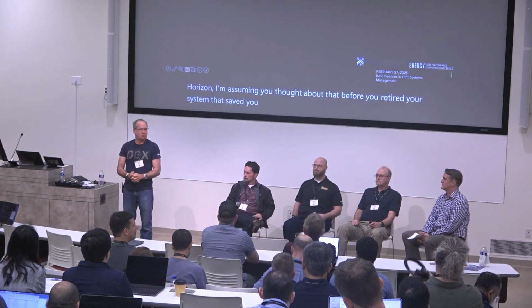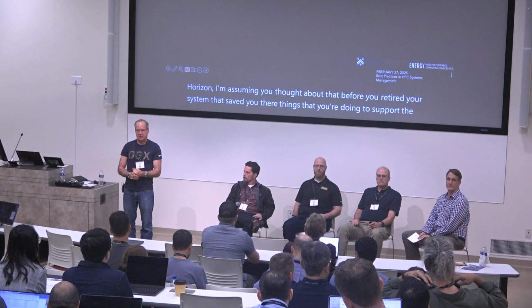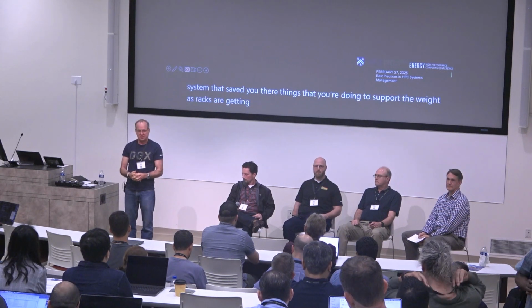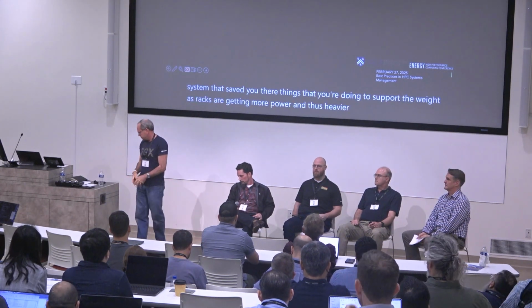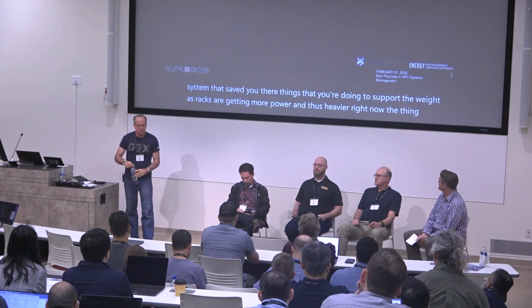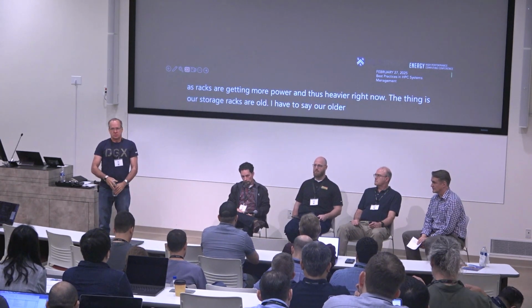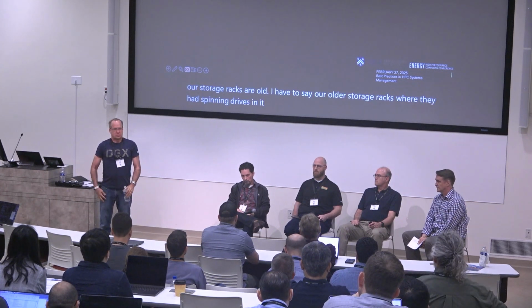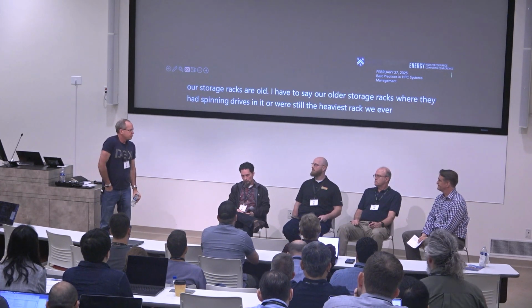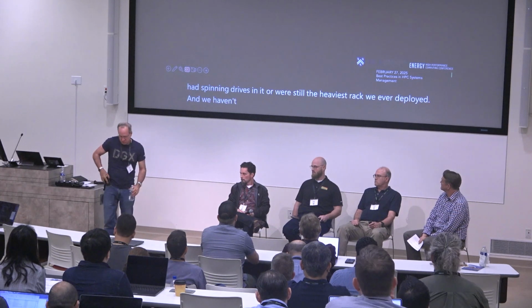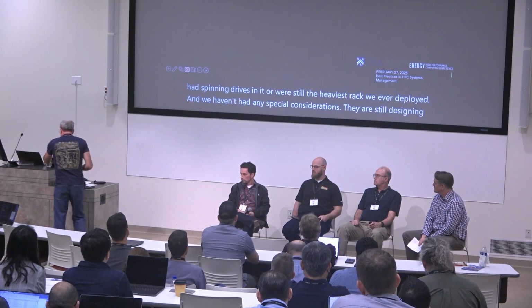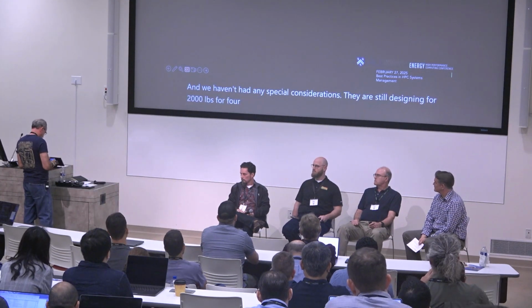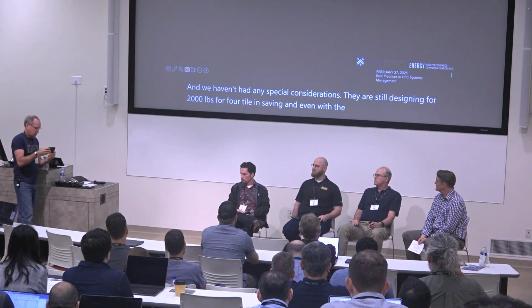Things that you're doing to support the weight as racks are getting more power and thus heavier. Right, now the thing is, our storage racks, the older ones with spinning drives, were still the heaviest racks we ever deployed. We haven't had any special considerations; they're still designing for 2,000 pounds per floor tile in Saby. Even with the liquid cooling, it's not adding a whole lot of capacity per rack. Keep in mind though, the racks are getting wider.